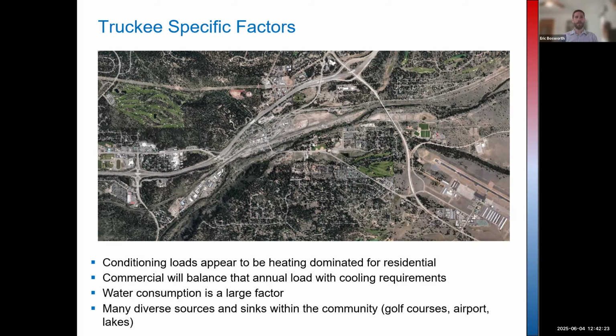Final point here: within the community, you have some interesting sources and sinks as well. I mentioned earlier that golf courses can make great areas to do heat rejection. So if you end up a little bit cooling dominated because there are a lot of commercial buildings included, that's a great way to pre-temper the irrigation water. You warm it up a little bit early in the morning from the loop, then put it through the sprinklers as you would normally, and that allows you to reject a lot of heat out onto the grass and balance your thermal loads. It's a very cheap and effective way to get a lot of additional capacity out of a system.